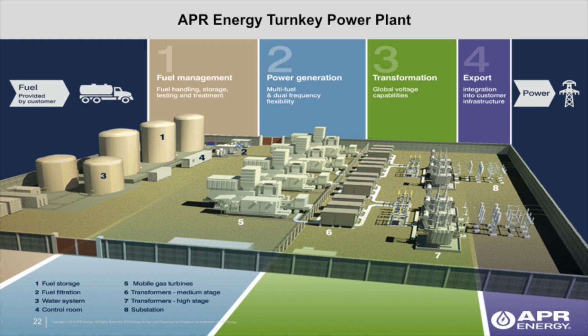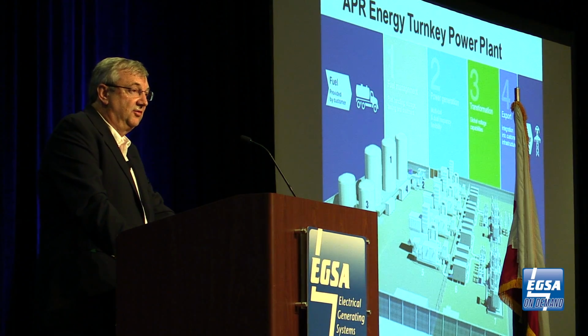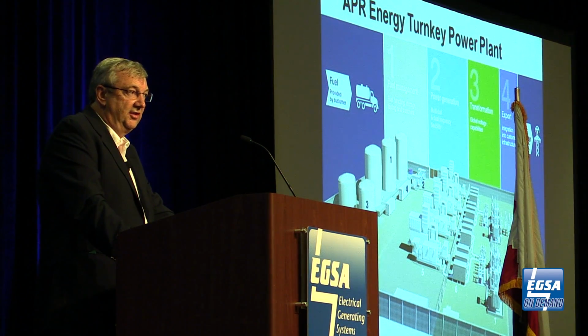Here we have our single phase transformers again, but these are high voltage transformers, oil filled, a 70 MVA block. You have to go into oil at those voltages. That transformer system will then take 33 kV or 34 kV all the way up to 138 kV, 60 hertz, and that has to be done inside oil.